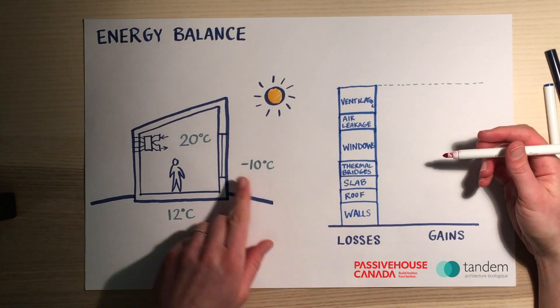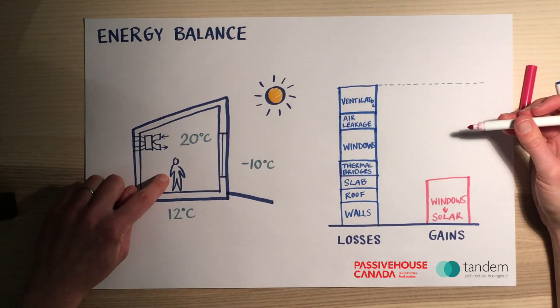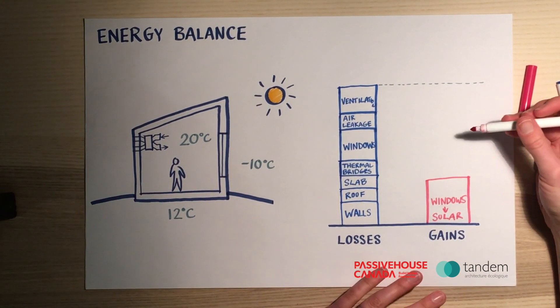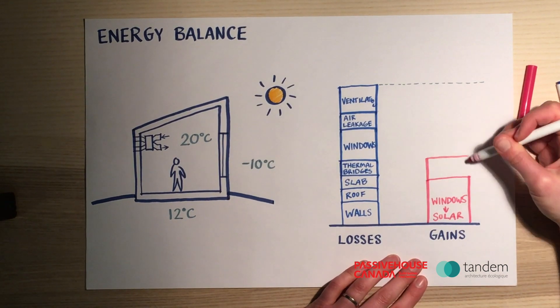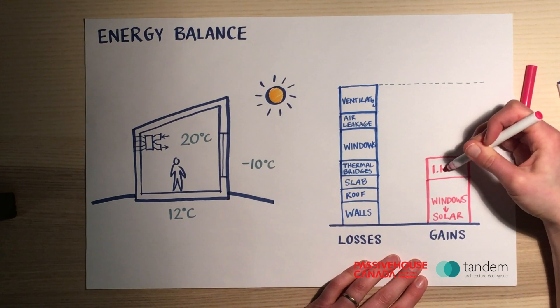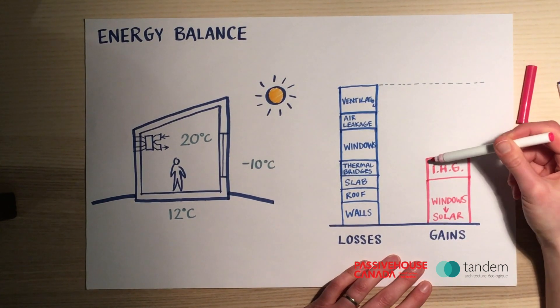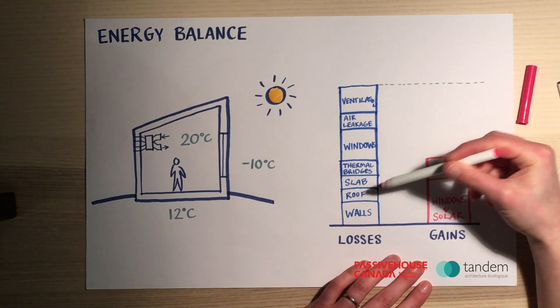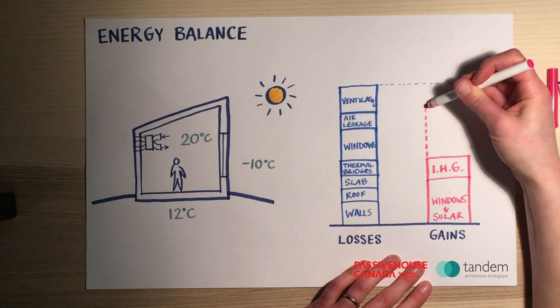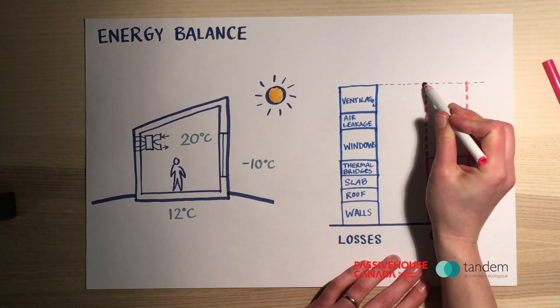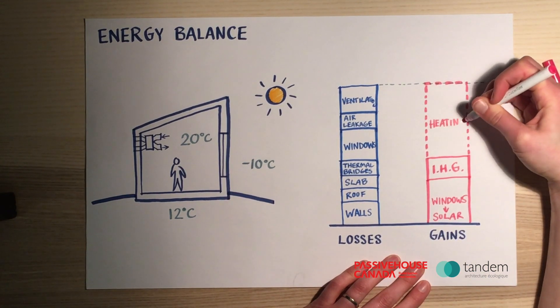We will have solar gains attributed to the windows. We will have interior heat gains, which are any heat gains associated with the human beings in the building — they all give off heat — and any waste heat from equipment, building equipment, appliances, and lighting. The rest of the gains will be balanced out by the heating system, whose job is to compensate for the difference between losses and gains.